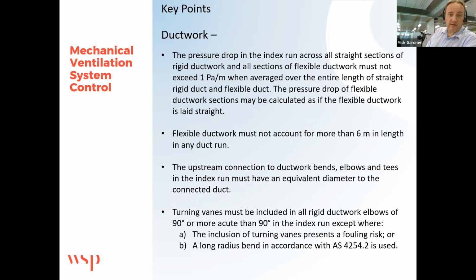They're also now saying flexible ductwork must not exceed 6 meters in length in any duct run, which is still quite a high run. Upstream connections of ductwork bends in the index run must have equivalent diameter to the connected duct, and turning vanes must be included in all rigid ductwork elbows of 90 degrees or more acute than 90 degrees in the index run, except where there's a fouling risk or long radius bends are used.